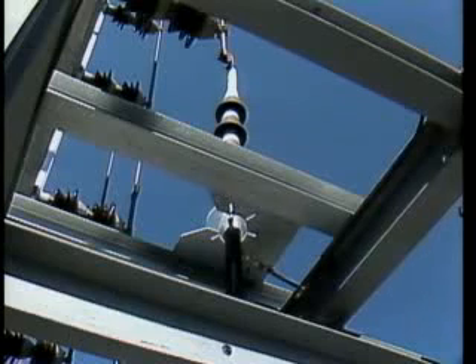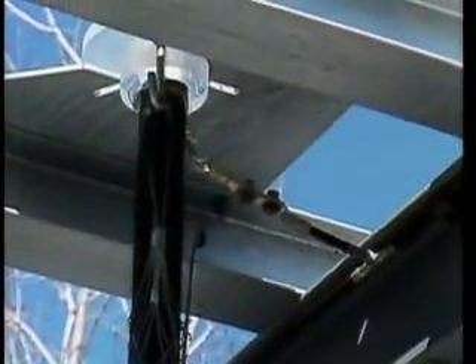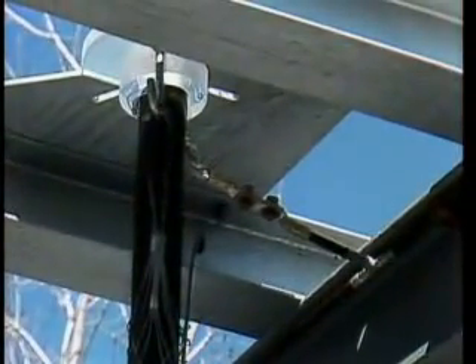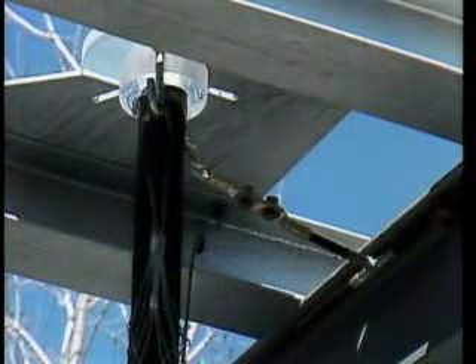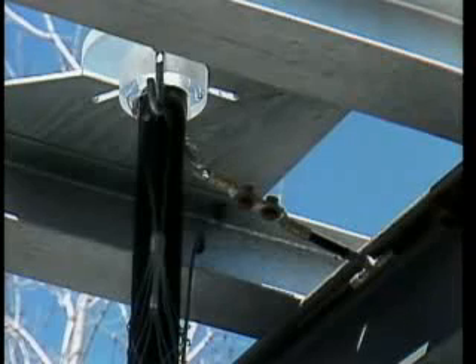Finally, a high voltage termination may need to reduce the voltage stress that can result in corona discharges around the outer surface of the cable. This is done by connecting the metallic cable shielding to ground. This allows any voltage on the insulation shield to drain to ground and keep the outer surface of the cable at or near ground potential.